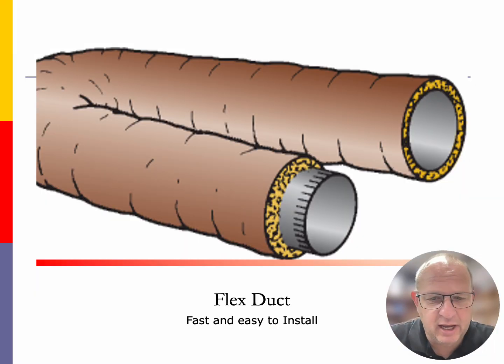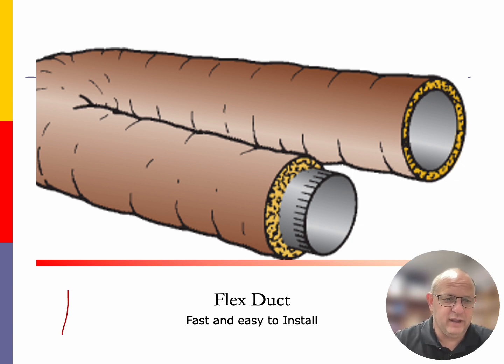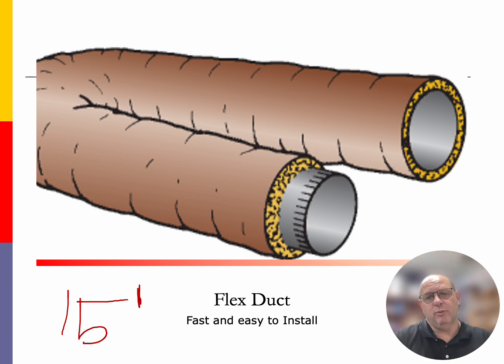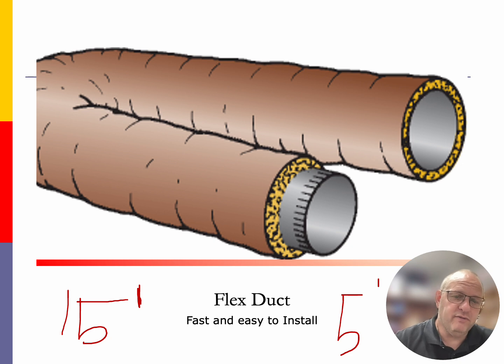Flex duct is an easy, fast way to install our airflow. The only problem with flex duct is there is a limit to how far you can run flex duct. Okay, so that limit is 15 feet for residential. Residential applications is 15 feet. A lot of commercial applications, you are going to be running no more than 5 feet of flexible duct. And they do this for a purpose, and that purpose is that the flex duct restricts airflow quite a bit because of the ridges on the inside.